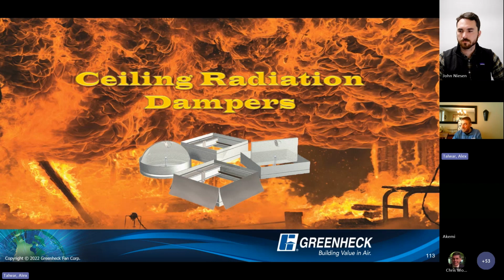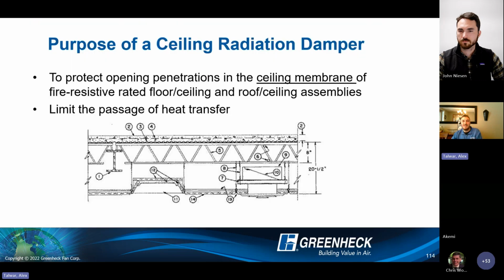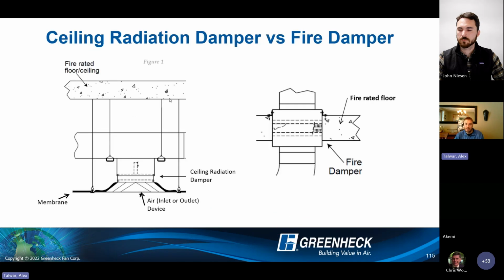And then I did just have a little time for ceiling radiation dampers. Chris asked me to include these as well. So I do want to retouch on these real quick. So again, talking about protection of a ceiling membrane of a fire resistant rated floor ceiling or roof ceiling assembly, not a through penetration ceiling membrane of a rated floor ceiling or roof ceiling assembly. And we are limiting the passage of heat transfer. There we go, nice red arrows there.